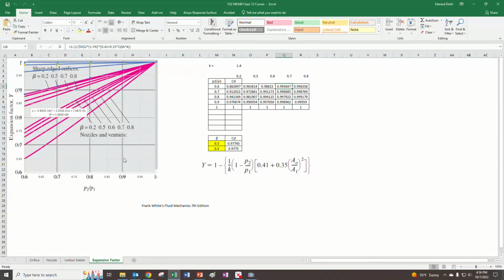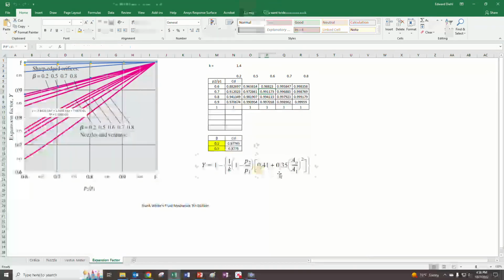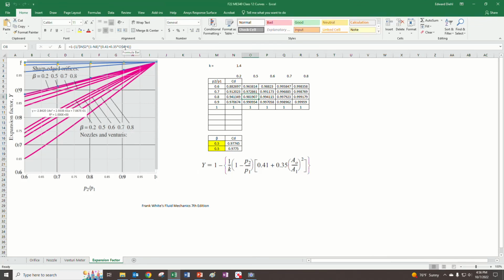Yeah, they got the expansion factor right here, so you can see it yourself. And see, this is my P1. But here's P2 versus P1, just as a ratio of the things. And you can see where they line up on the curve right here. I can't figure out, see, this is the equation that I have. And here's my betas in here. My beta is fourthed, right? My beta is at 0.5. And I can't figure out why this curve isn't working out the right way.